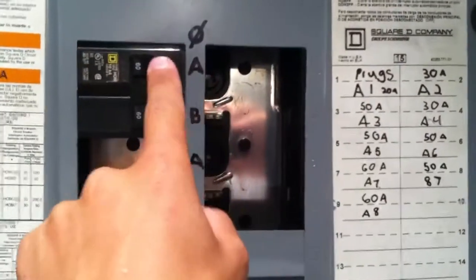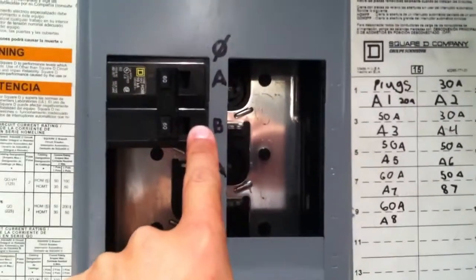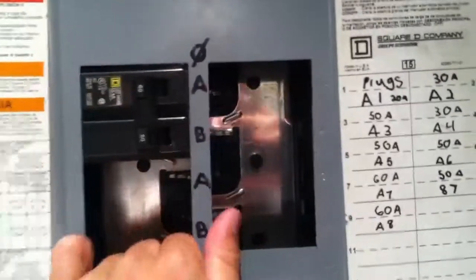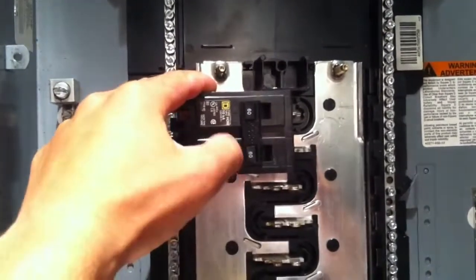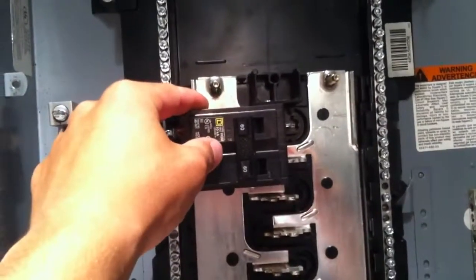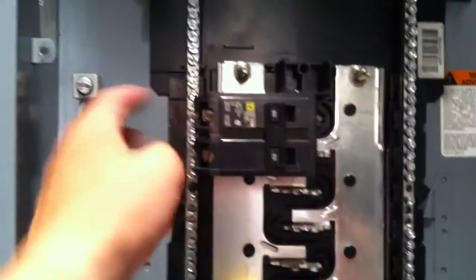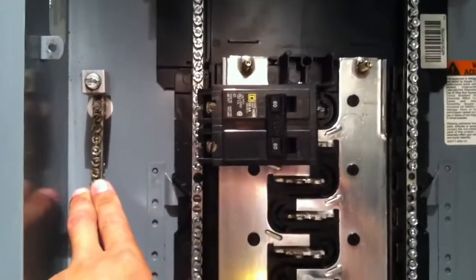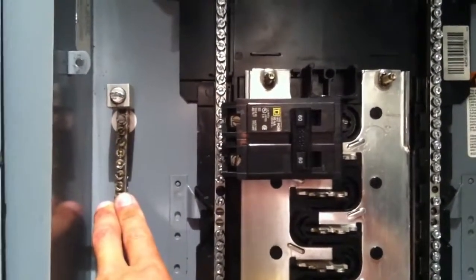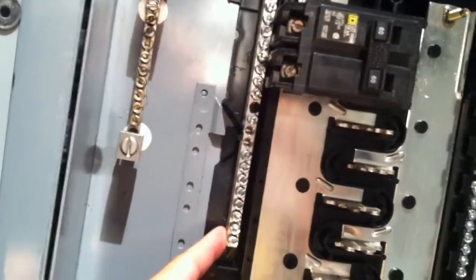It goes. This breaker is pulling from phase A, this breaker is pulling from phase B right there, alright? So it's pulling from both hot legs. This would run something like, as I said, an air conditioner or something. If the appliance only needs 240 volts, typically it just has two hot lines and a ground. But sometimes it does have little things inside it that do require 120 volts, in which case you would just have a little neutral go along with it.